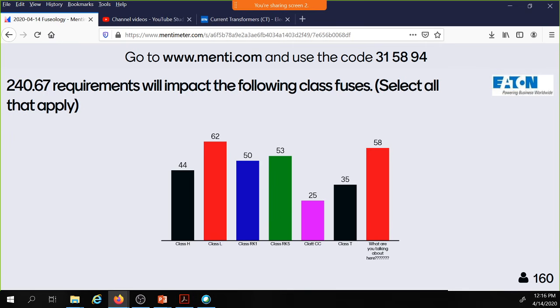The key thing to remember, 240.67 impacts all fuses 1200 amps and above. So a lot of the fuses that I have listed there, especially the CCs, the Charlie Chaplins, don't go above 30 amps. So it definitely would not impact the CC fuse. The Class T fuse, I believe we do make, the largest Class T fuse is a 1200 amp fuse, so that could be impacted. The Class Ls, definitely, those are big boys. L is for large. And we're going to go through each of these classes. Class L and Class T are the two big ones in that list.